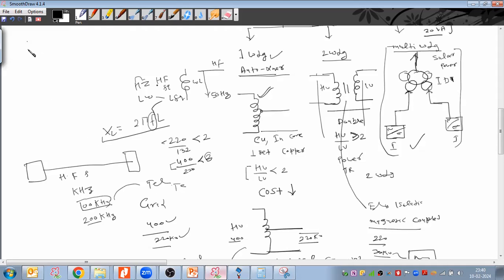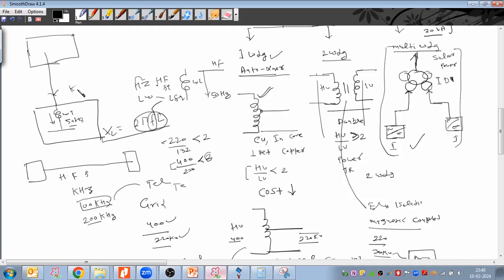So in one substation, the high frequency signal is coming to the next substation. I'm putting a wave trap equipment here, and after that connecting to the bus bar. This wave trap equipment will allow the 50 Hz signal to pass, because at 50 Hz the frequency is less, so overall impedance will be less. When a high frequency signal comes, in kilohertz, the frequency is high, so the XL would be too high, and it will stop the high frequency communication signal, diverting it to the communications equipment in the substation.